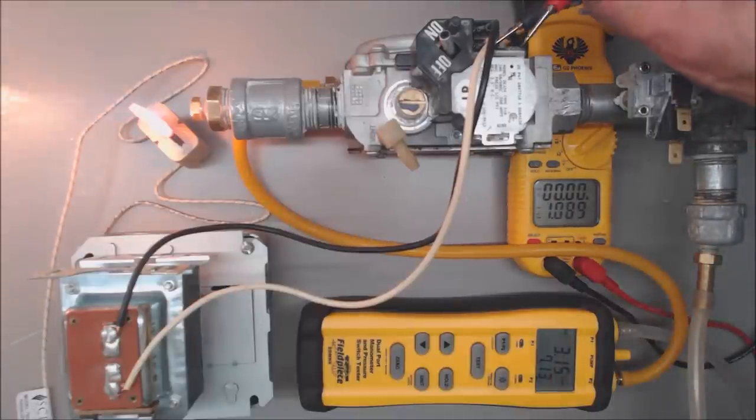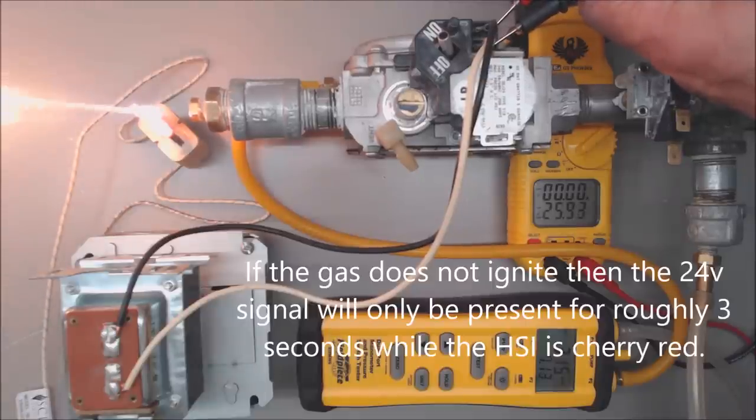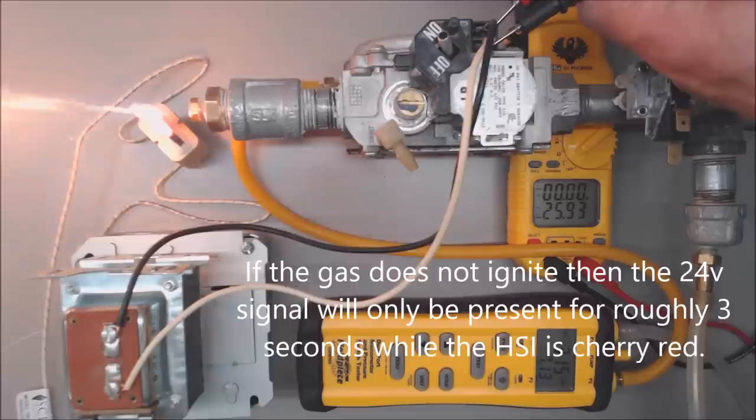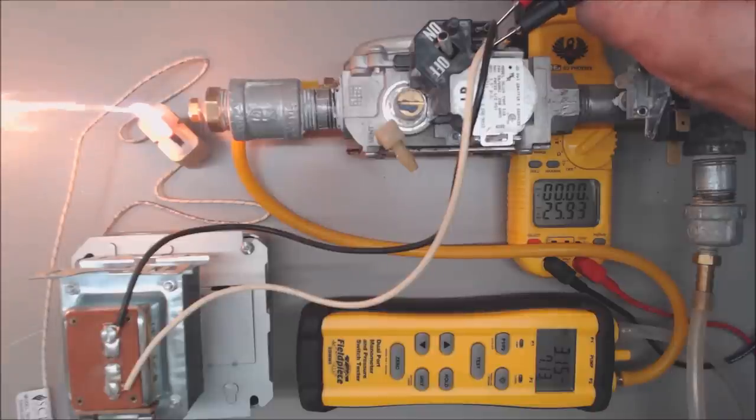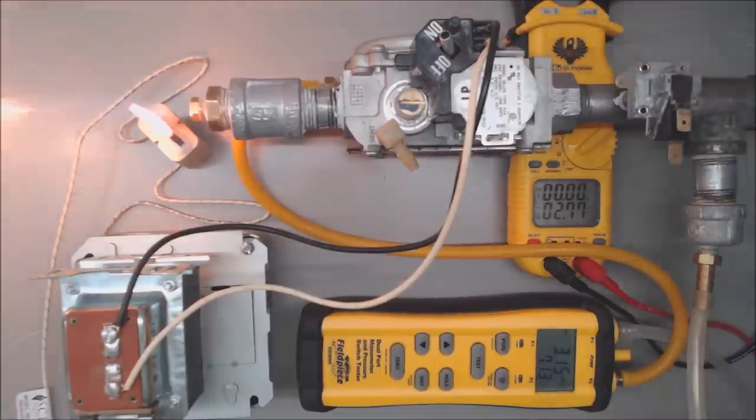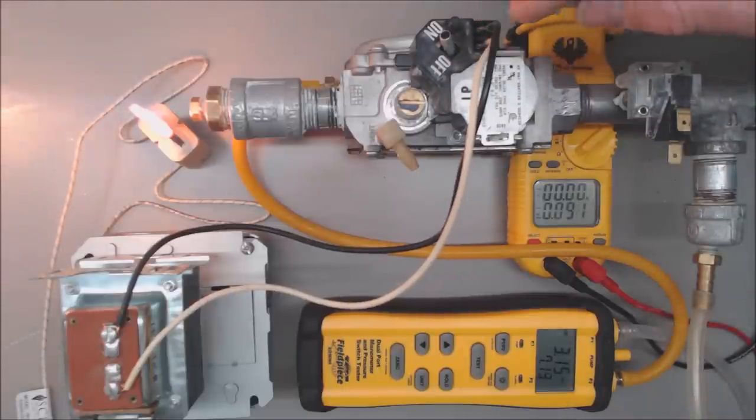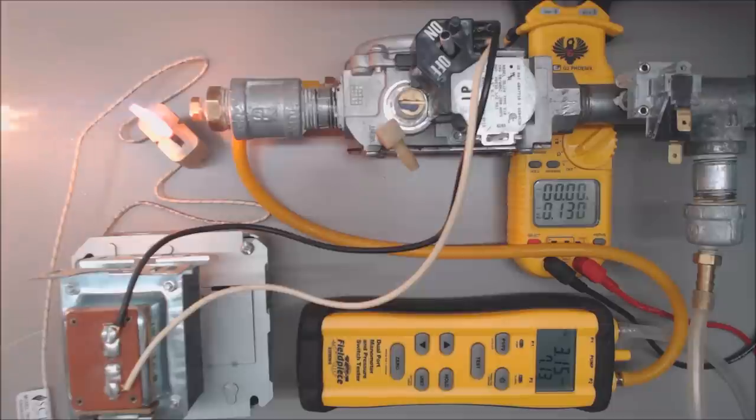Make sure that you don't go from this ground onto the hot wire, and we're going to read 25.9 volts heading into the gas valve right now. You want to watch that voltage, make sure that's not dropping. Also check your 120 volts. Just make sure that while there's a load on that furnace the voltage is not dropping. So as long as you have steady voltage going to your gas valve then the voltage is not the problem. It's just the actual output gas pressure.